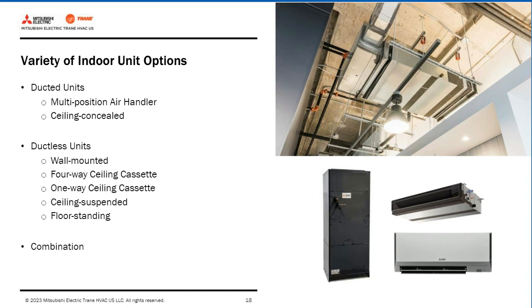Another helpful feature of the VRF systems is just the variety of indoor units you can use, whether you're looking for more ducted options or ductless options. That gets used a lot in some of the older buildings that have real high ceilings where you can't pass ductwork through spaces. VRF tends to be a good option for that, being that you can just run the refrigerant piping in a lot smaller area to get it into spaces, and not even needing ducted options by using some of our cassettes.